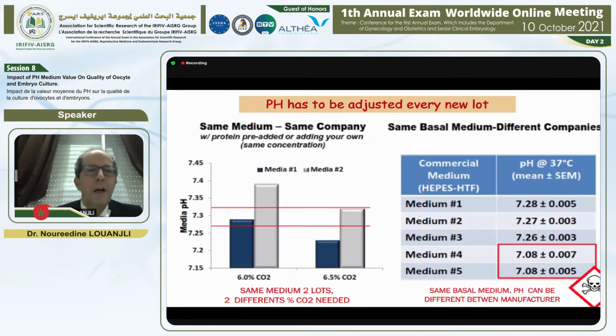Here, for example, we have the same company and the same medium, but two lots. If one lot works at 6% CO2, the other lot must have 6.5% for the same target pH, 7.3. We have to check every new lot. We have to check the pH even for different companies with the same basal buffer. On the right, you see for HTF basic medium, you have a different pH depending on the company. You have to check your pH, even for the handling medium based on HEPES or MOPS.